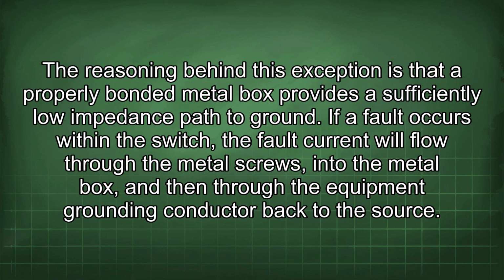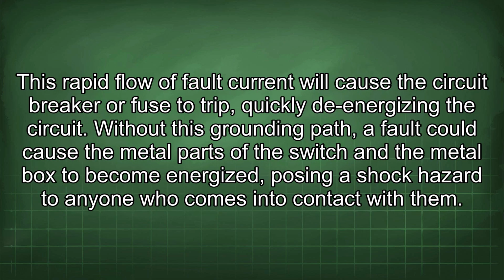The reasoning behind this exception is that a properly bonded metal box provides a sufficiently low impedance path to ground. If a fault occurs within the switch, the fault current will flow through the metal screws into the metal box, and then through the equipment grounding conductor back to the source. This rapid flow of fault current will cause the circuit breaker or fuse to trip quickly, de-energizing the circuit. Without this grounding path, a fault could cause the metal parts of the switch and the metal box to become energized, posing a shock hazard to anyone who comes into contact with them.